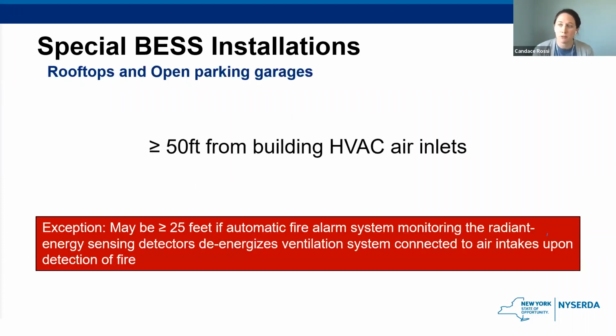And then for both rooftops and open parking garages, you want to make sure that they're at least 50 feet from the building HVAC air inlets. These can be made smaller if the automatic fire alarm system monitoring the radiant energy sensing detectors de-energizes the ventilation system connected to the air intakes upon detection of a fire. But once again, you're just maintaining space around these systems.